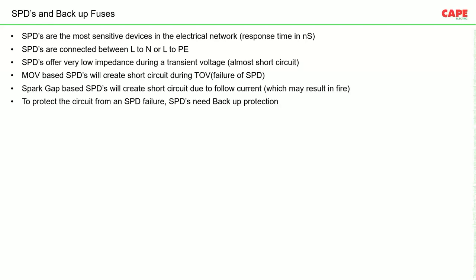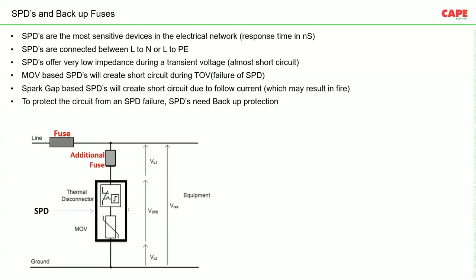Every SPD will eventually reach end of life. There are two possibilities: it may fail in open circuit mode — in which case it simply disconnects from the circuit with no problem — or it may fail in short circuit mode, where short circuit current flows from the line through the SPD to ground. The resulting energy dissipation is very high, and the SPD can catch fire. We must ensure that the SPD is disconnected from the circuit as early as possible.